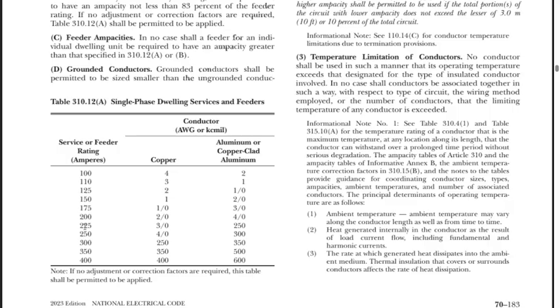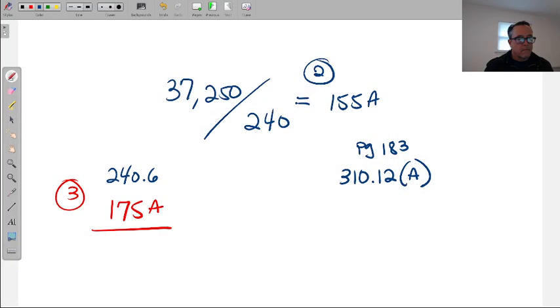It'll be a 1/0. Our 175 is a 1/0. So I'll put it over here, 1/0, and this is question 4. Just want to double check, make sure that's the correct answer. Yes, it's also the correct answer on it. It didn't change because question 3 and question 4 are both 175, and we fall with the 1/0 as well.